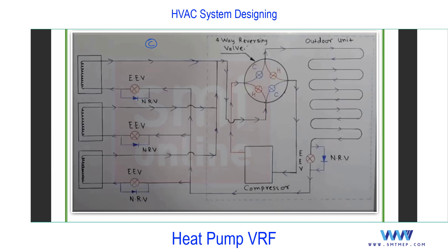You can see the four-way reversing valve. Inside it you'll find four valves. For cooling mode, two valves will be closed. If you switch to heating mode, those two valves open and the other two close. Apart from this, for all indoor units you'll find an NRV - a non-return valve. The rest of the system is the same.